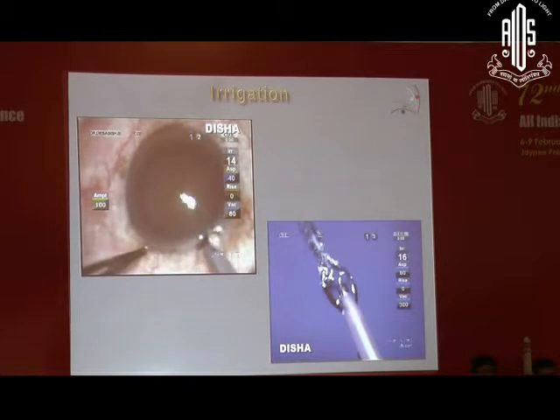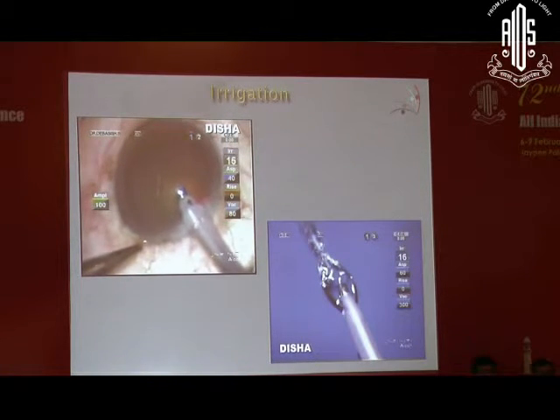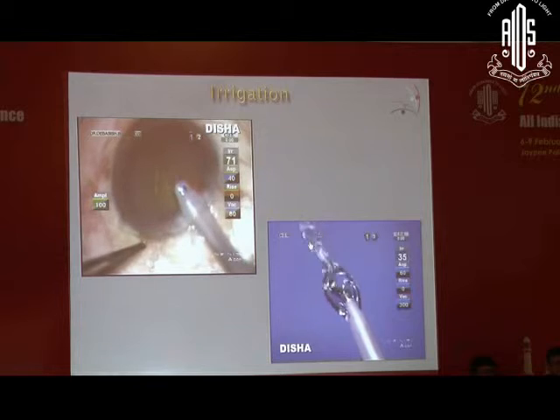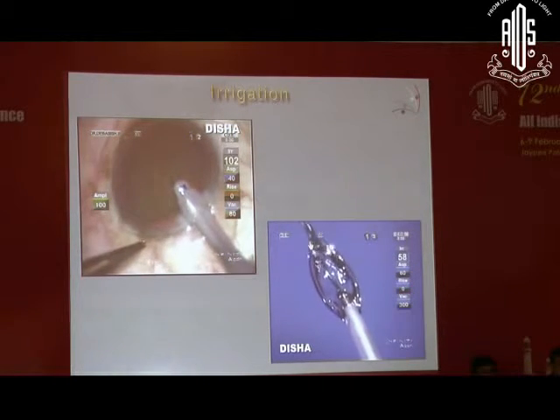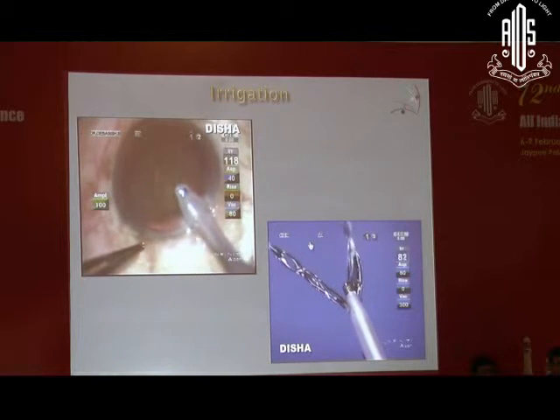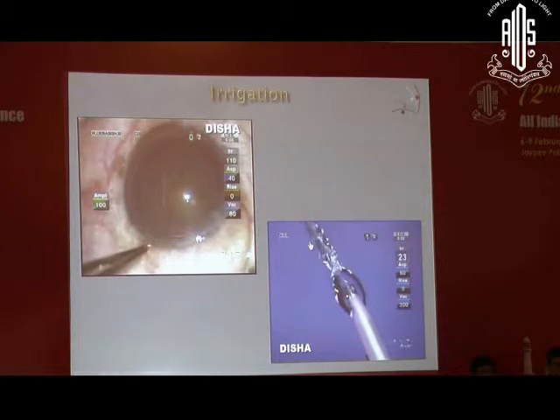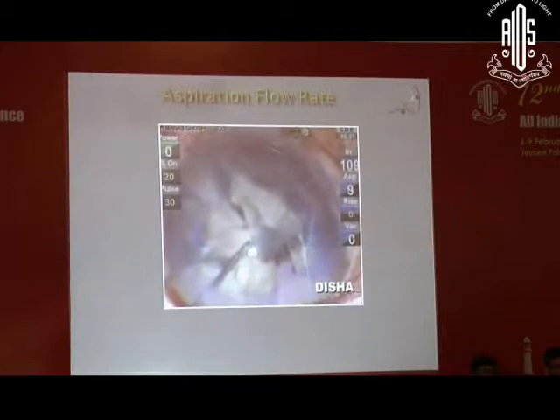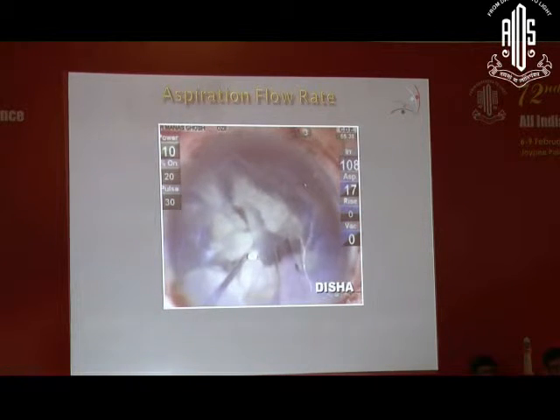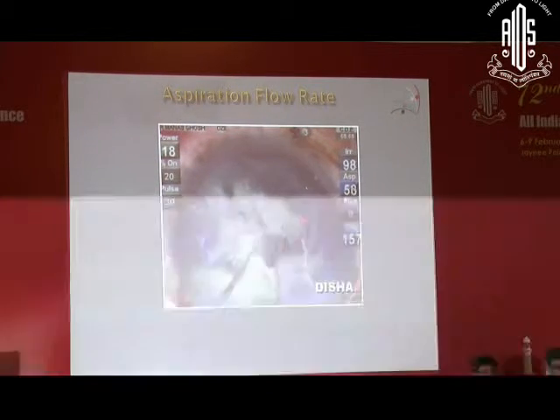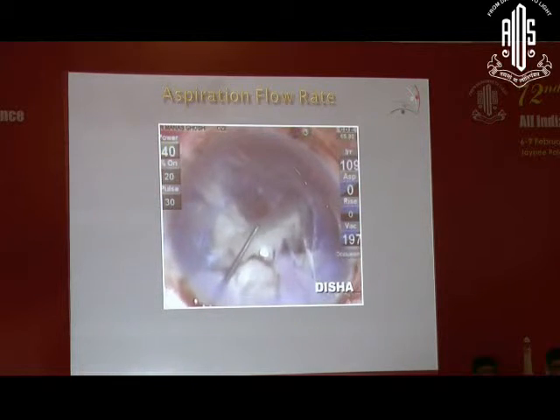Now this is to show that if we increase the irrigation, we are actually lifting the bottle height. See, the irrigation increases and the chamber deepens. So this is to say that irrigation is passive, it is just dependent on the bottle height. Now to give you an example of the aspiration flow, you can follow the parameters here. As we raise the aspiration flow, this fragment which is not near, we are not moving the tip, not moving the fragment, we increase the aspiration and it has come to the tip.